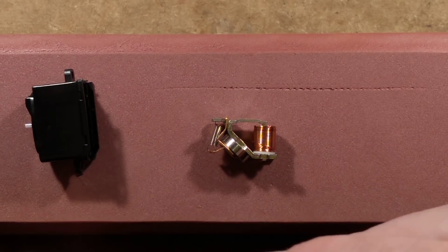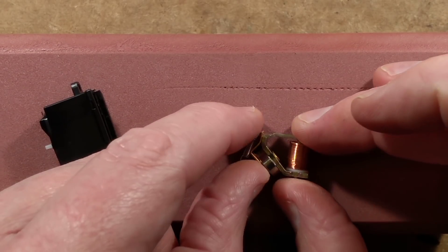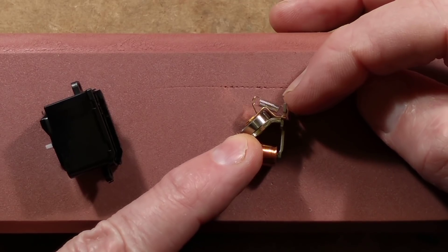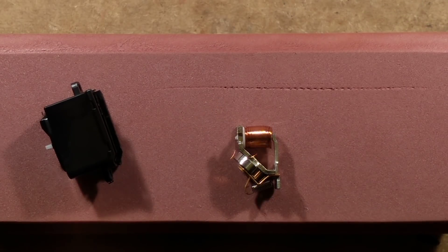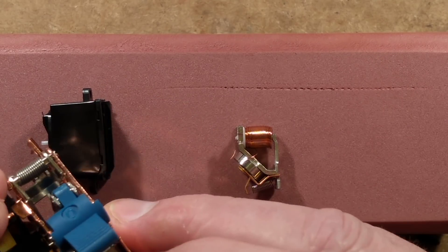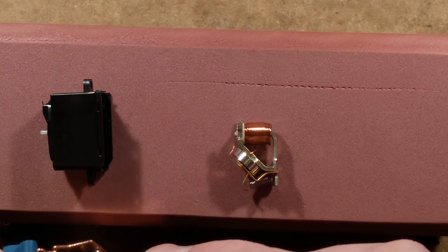Anyway, less politics — here is the little coil. I've removed the little white plastic disc; there was another one on top that I had to cut off because it came loose. When you reset the breaker and that little white pin gets pushed in, it pushes this spring-loaded pivot against the end of the coil. Because it's got residual magnetism it latches, but when a slight current bias is put in it unlatches and pings open with enough force to knock the trip plate and trip the mechanism out.